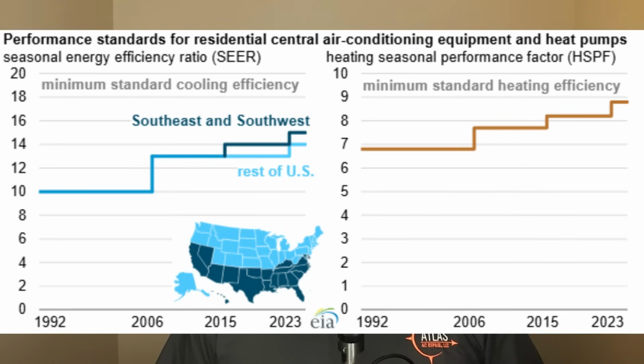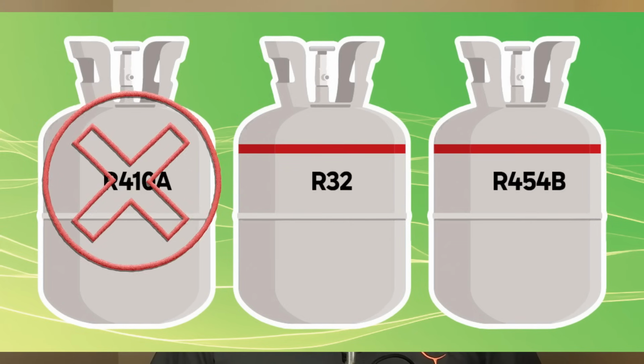In regards to equipment, we experienced two regulatory changes: an increase in minimum SEER ratings, along with another refrigerant change. Manufacturers had to move away from R-410A in all their new equipment, and the bulk of the industry adopted R-454B as its replacement. One manufacturer ended up going with R-32.